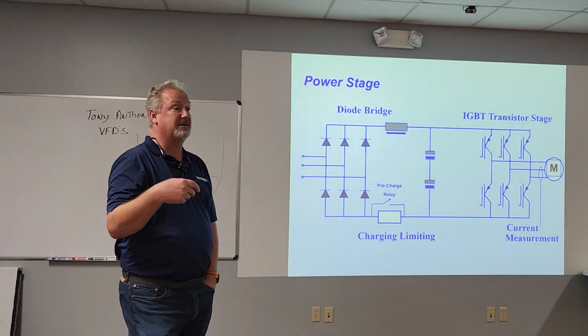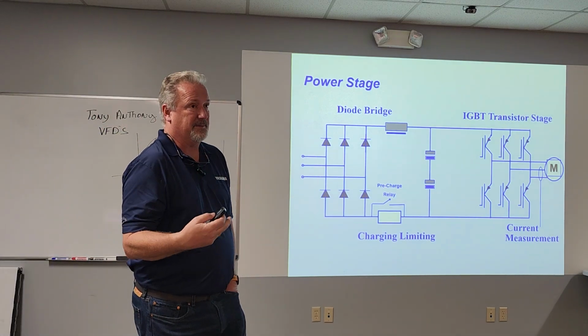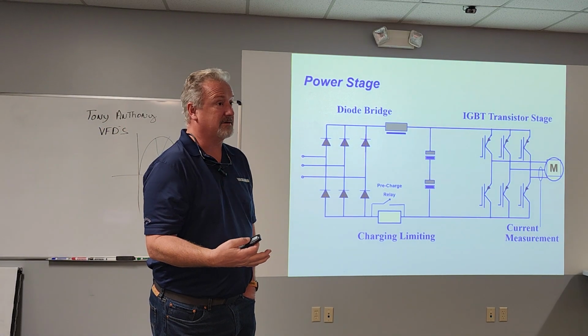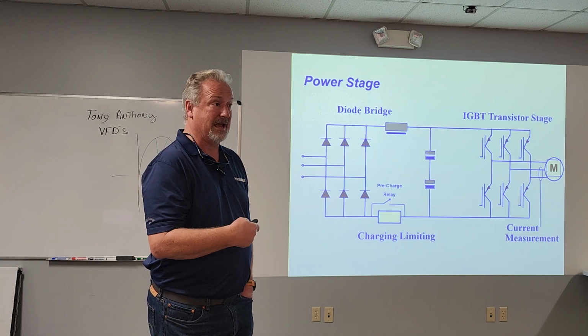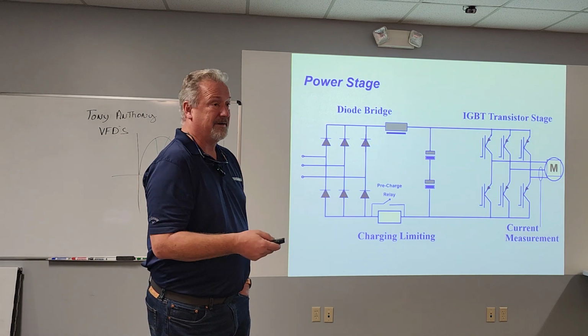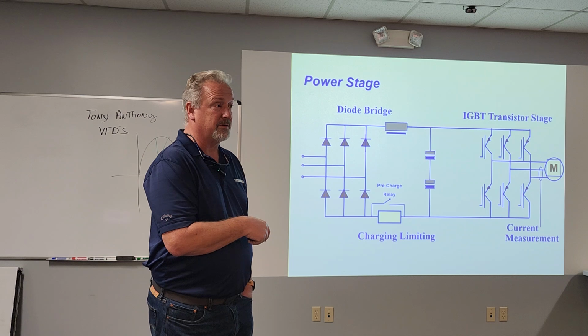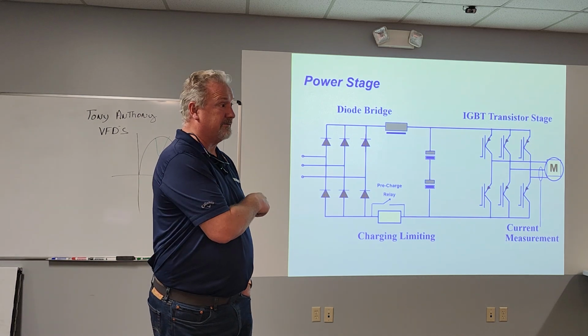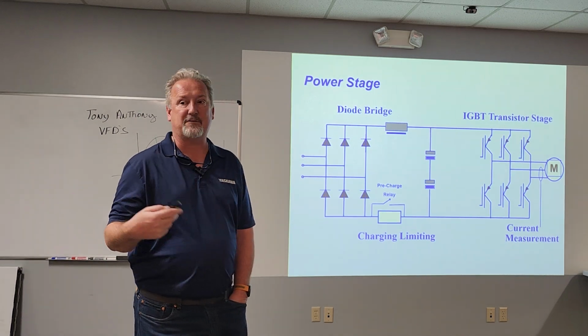This is really nice because if you get up to 5 or 10 horsepower single phase motors, they're expensive and you can't control them. You can run a 5 or 10 horsepower, 20 horsepower 3-phase motor using single phase in the drive as long as we size the drive properly.